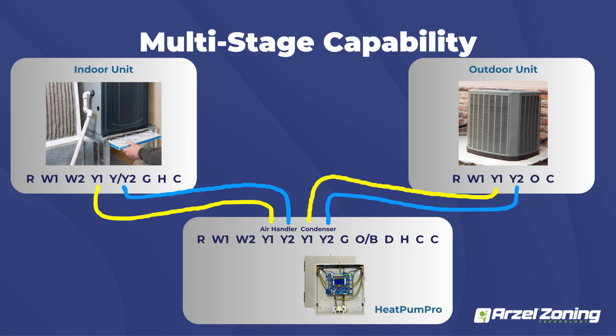And one of the things that the HeatPumPro also incorporates is a setting called zone weighting and air handler stage threshold. What that actually does is we're able to lock out second stage blower operation on individual zones. So you guys are able to pick a percentage of ductwork per zone, and then you are able to pick what percentage of ductwork you want actually open in that system before we can achieve second stage on your output. And the way that we actually handle that is we actually separate your Y1, Y2 air handler and your Y1, Y2 outdoor unit. So your condenser, heat pump, whatever you guys are using, those are separated.